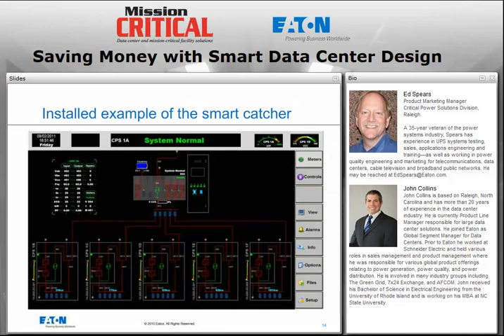Here's another shot of an installed example where you can see a little bit more clearly the primary UPSs. In this case, there's 5 of them, and the catcher UPS. And if you look where my cursor is along the right-hand edge of the screen, you see that not only are there buttons like metering and alarms and options and files and setup. This is all done in Windows, by the way. But you also see one for controls. So if the client does want to allow remote control of the system, some do, some don't, or they need it in certain places and they don't want it in others, then that capability can be used or not used depending on the client's philosophy.